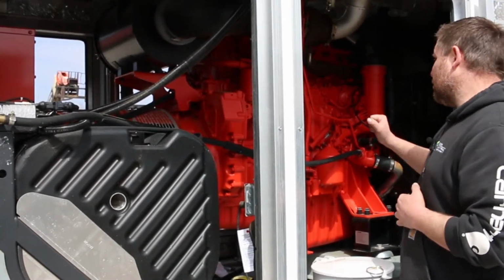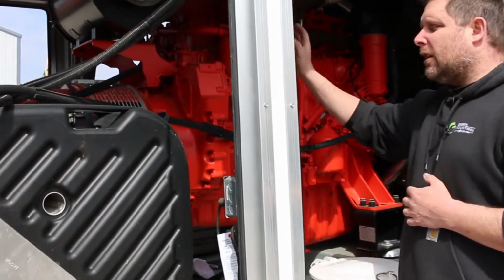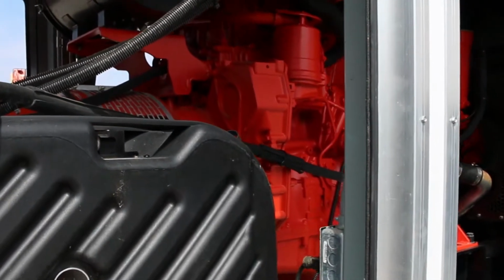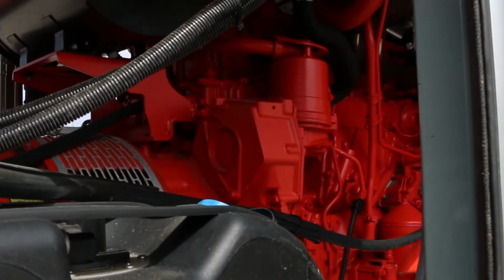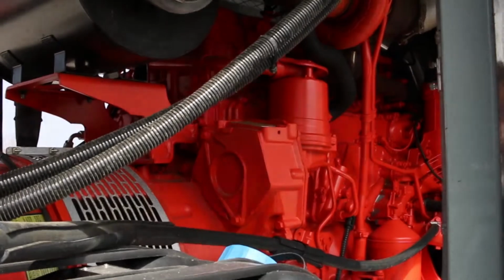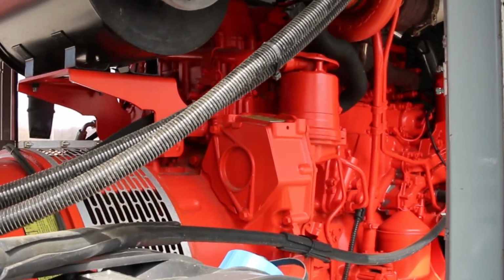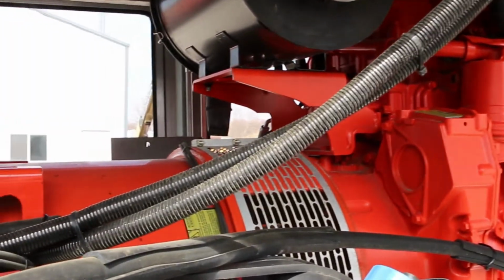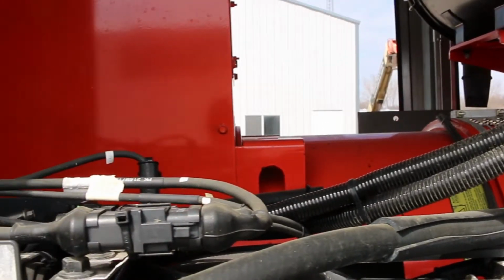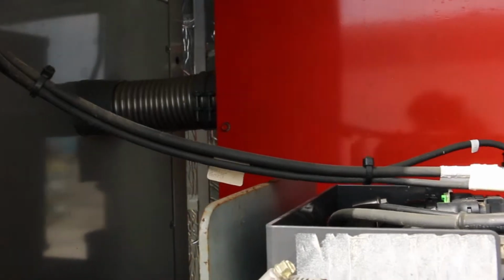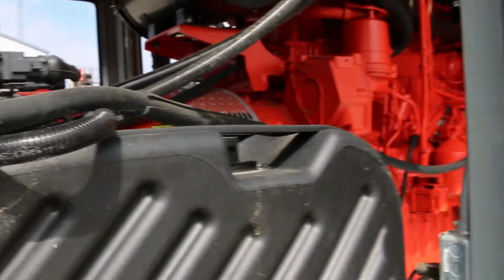Let's break it down a little simpler here. We've got a 5-cylinder diesel, turning a 230 kW generator end, currently wired to 120/208 volt, but it is a 12 lead gen end. It will do other voltages. However, the switch gear, which we'll show you in just a second, is currently wired for 120/208. I believe the bus is only rated for that, but there are ways to get these things to operate at 480 if that is the case for you.